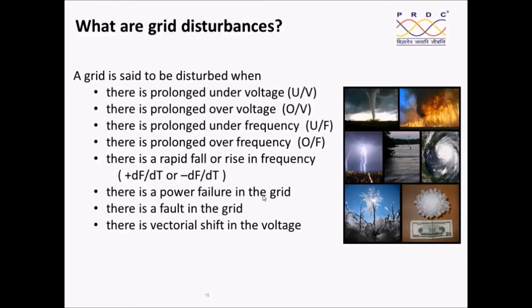There is a power failure in the grid. Assume that the grid itself has been lost. There is a fault in the grid. Again, the fault can be at many places. Therefore, depending upon where the fault has occurred, we should again get islanded, depending upon the quantum of fault current we are feeding to the grid.